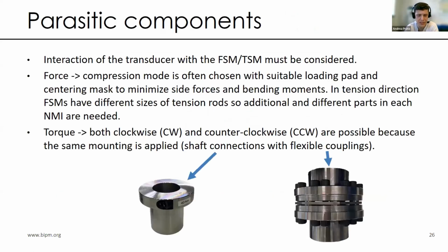Regarding parasitic components, this is another very important parameter which has to be considered, and this is due to the interaction between the transducer itself with the standard machines. For force, we usually perform compression mode comparisons because it is very easy to decouple the transducers from the interaction with the machines and interactions with external forces and bending moments. And also the mounting is much easier because we can use a suitable loading pad and centering masks that can minimize the effects of side forces and bending moments.